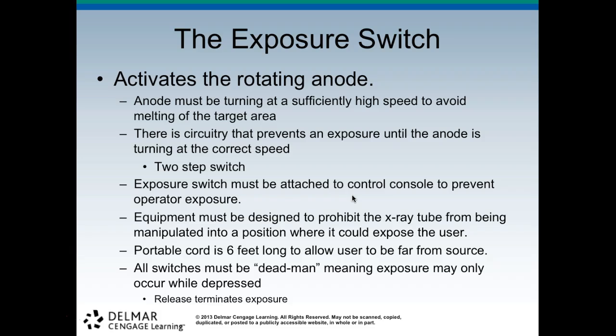The exposure switch must be attached to the control console to prevent operator exposure. So when we come into your facilities and we see that the exposure switch isn't mounted to your control panel, we will zip tie it so that it is, and it's actually a Title 17 law that you have to have it attached. Equipment must be designed to prohibit the X-ray tube from being manipulated into a position where it could expose the user. So you can't have the X-ray tube pointing at you when you make the exposure. And a portable cord is 6 feet long to allow the user to be far from the source. All switches must be dead man, meaning the exposure may only occur while depressed. So if you drop dead while you're making the exposure, it terminates the exposure, which is great, right? So hopefully you don't drop dead.